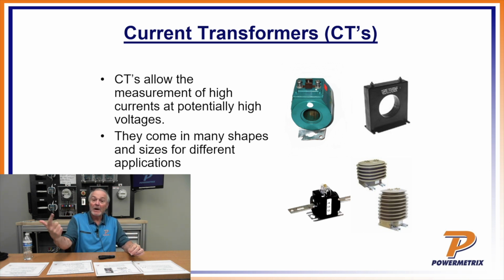So when you run the drive cable through it to boost it so that I can go to a dead site and I can still test the CTs, I would use the donuts, right? So I'm going through the donuts and I can use a drive cable. But if I have that bar type, I can't. So that's why we also have the clamp-ons in there so you can clamp onto those bars on either side. Okay.